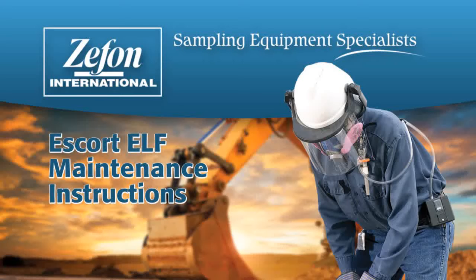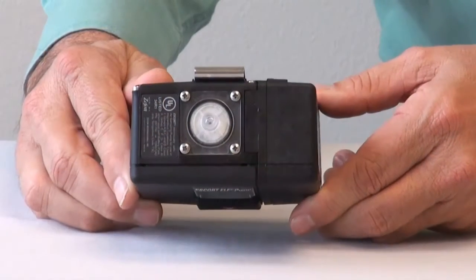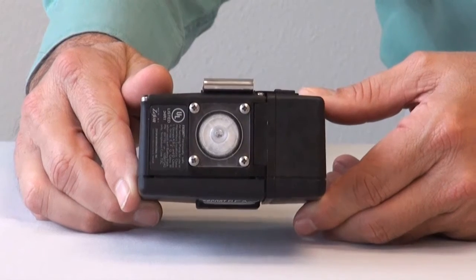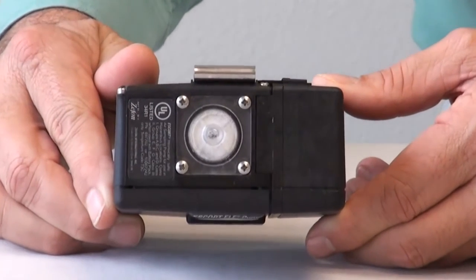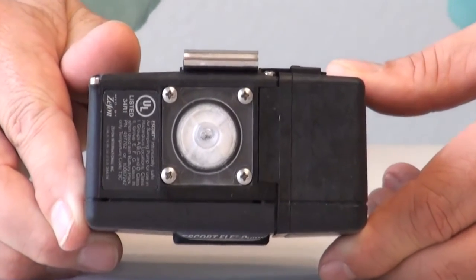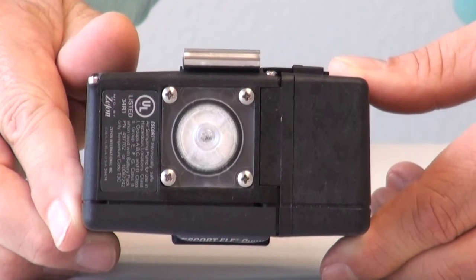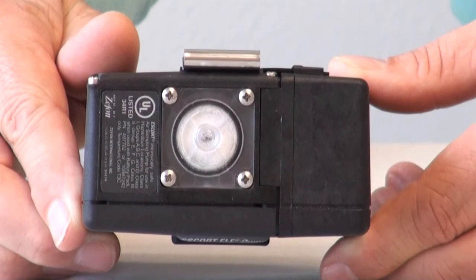This video is a basic guide to the routine maintenance of Zefon's Escort ELF personal air sampling pump. These instructions are also available in the operating manual. Before you begin any sampling, you need to check the inlet dust filter. If the filter becomes clogged, the sample flow might be blocked or an extra load is placed on the motor and reduces the operating time.